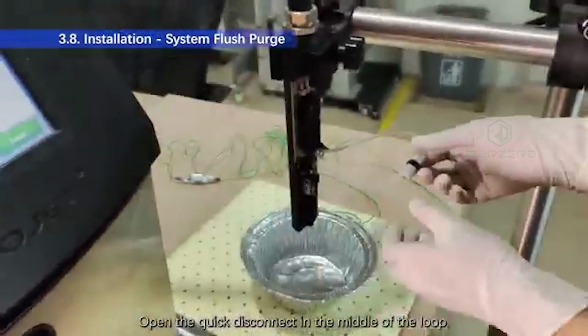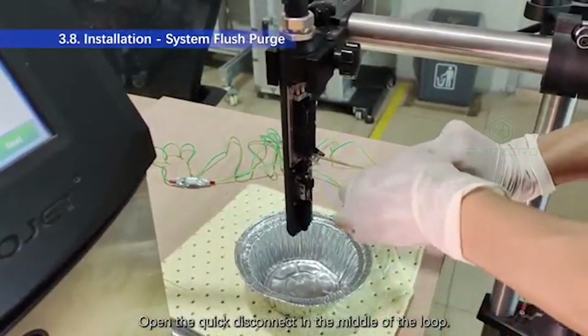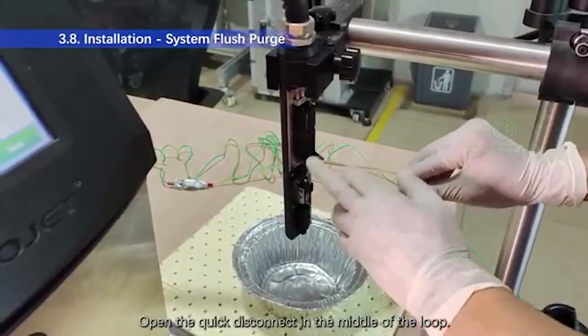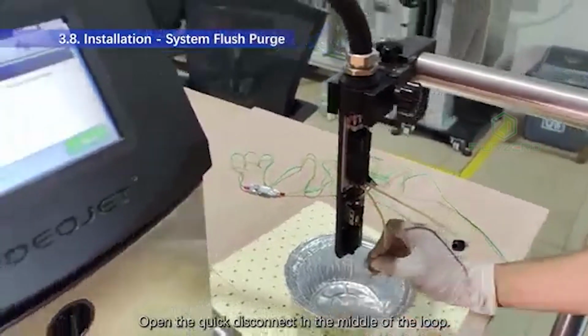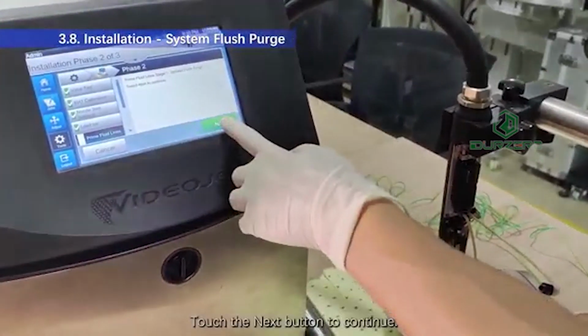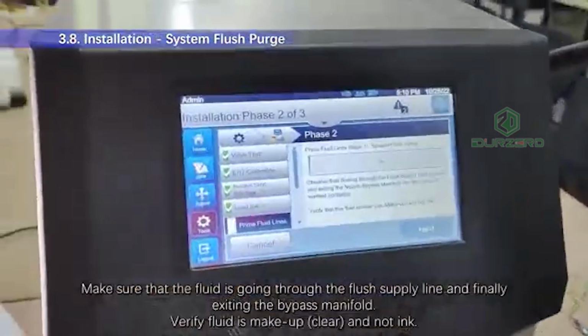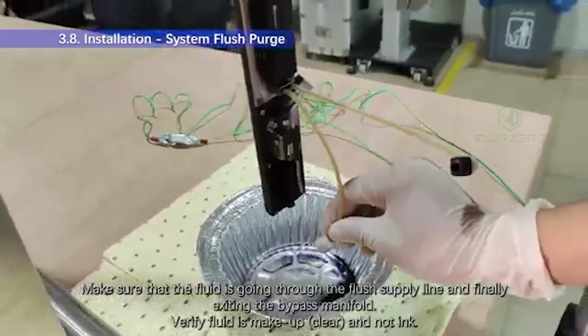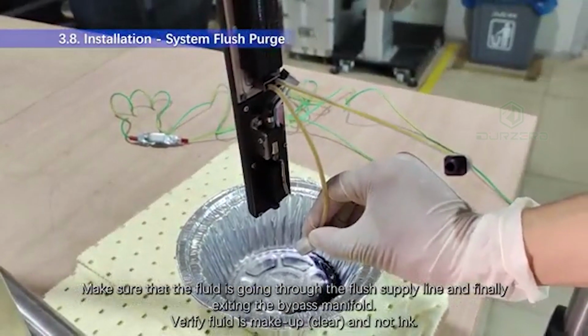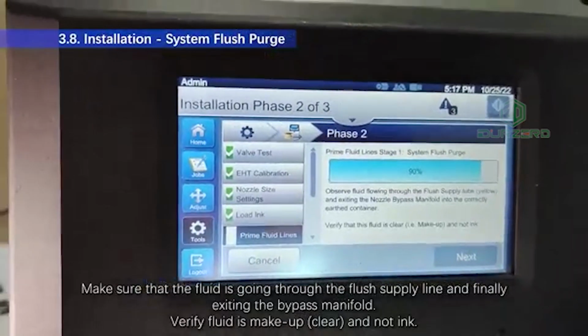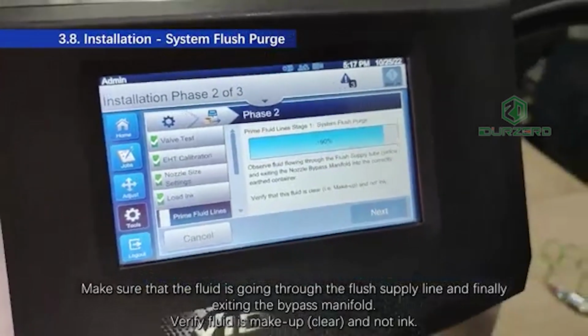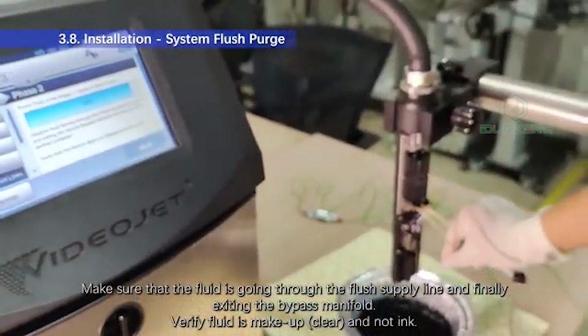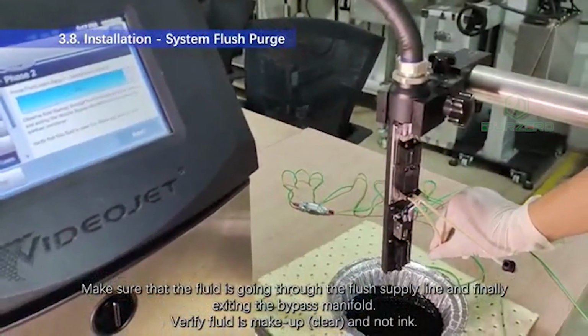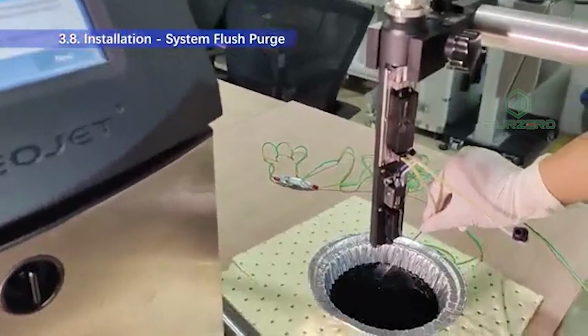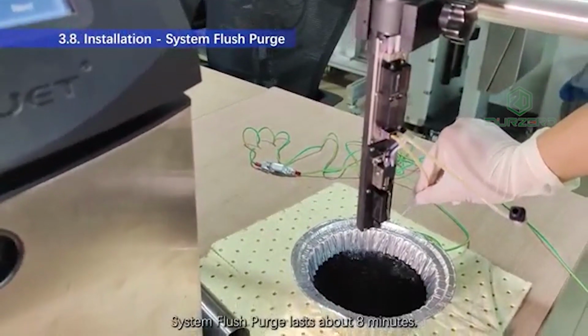Open the quick disconnect in the middle of the loop. Touch the next button to continue. Make sure that the fluid is going through the flush supply line and finally exiting the bypass manifold. Verify the fluid is makeup, clear, and not ink. System flush purge lasts about 8 minutes.